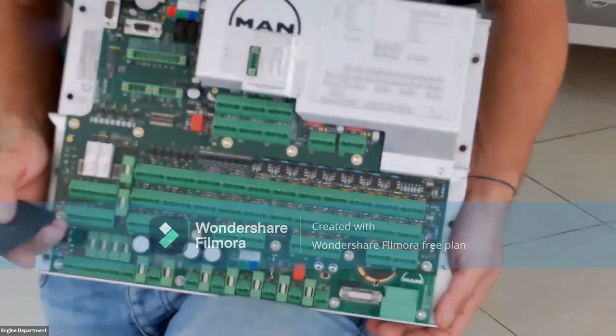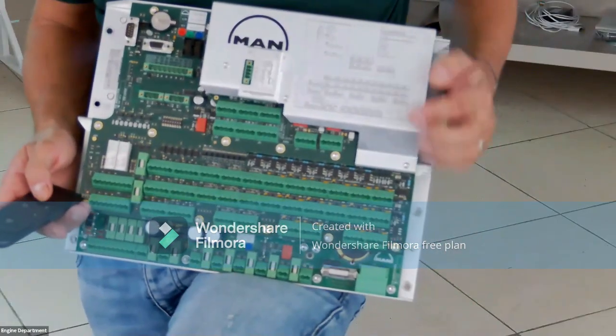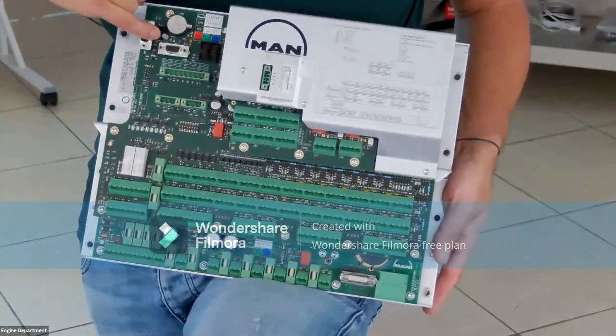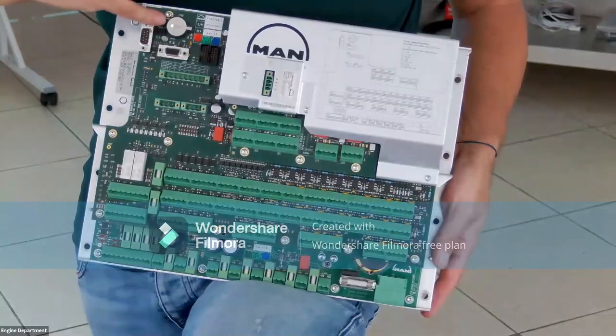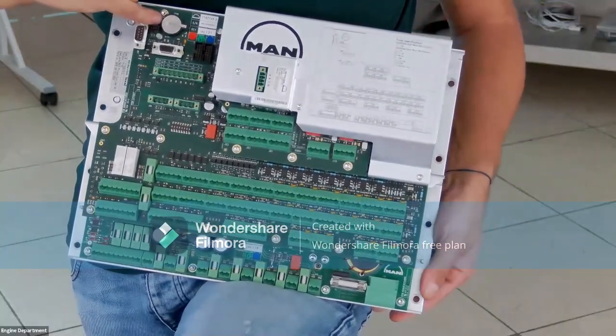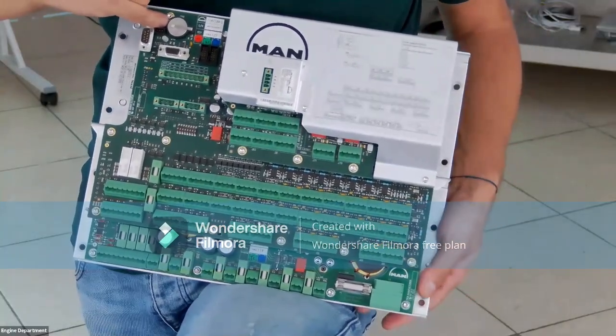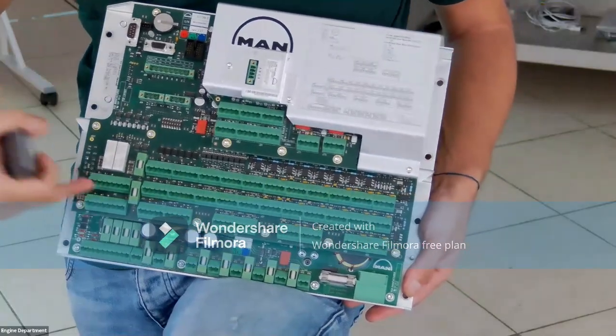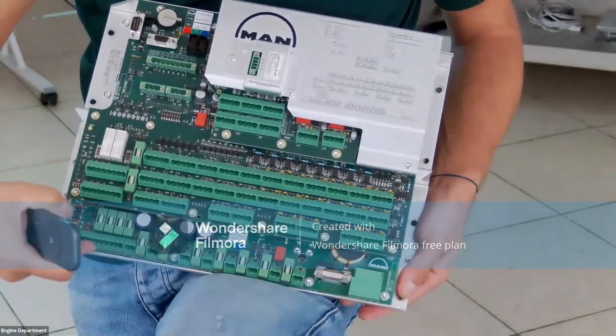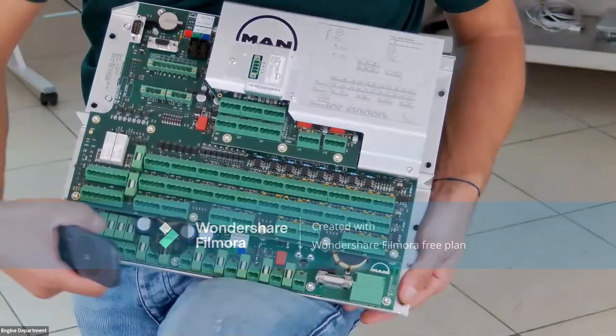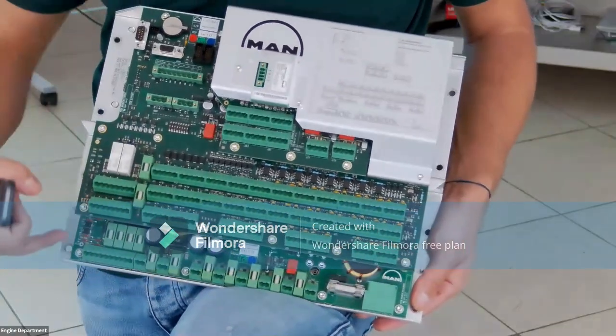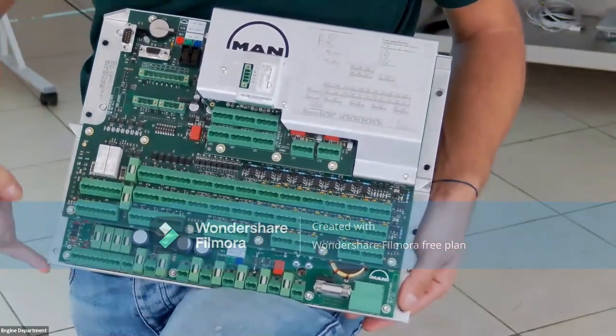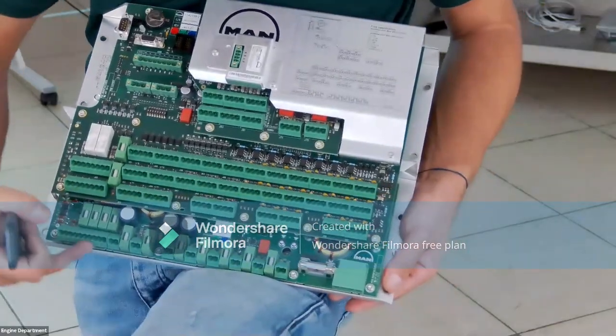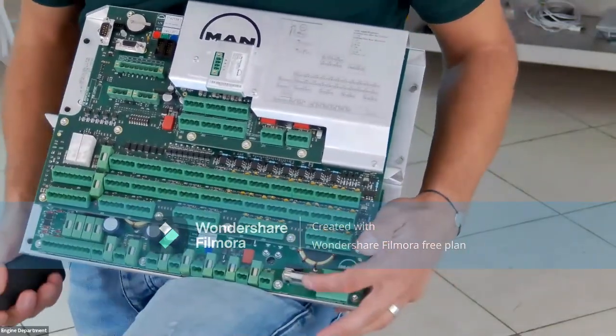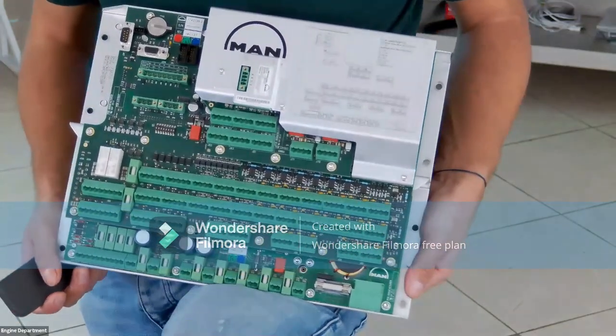Okay, so gentlemen, what are the components of the MPC? We have this LED indicator, now switched off. The battery, as I told you, is not a critical piece of equipment. It's used just to keep the internal clock of the MPC. We have the power supply board where you find all these fuses which protect the different channels, and the main fuse of the power of the MPC.